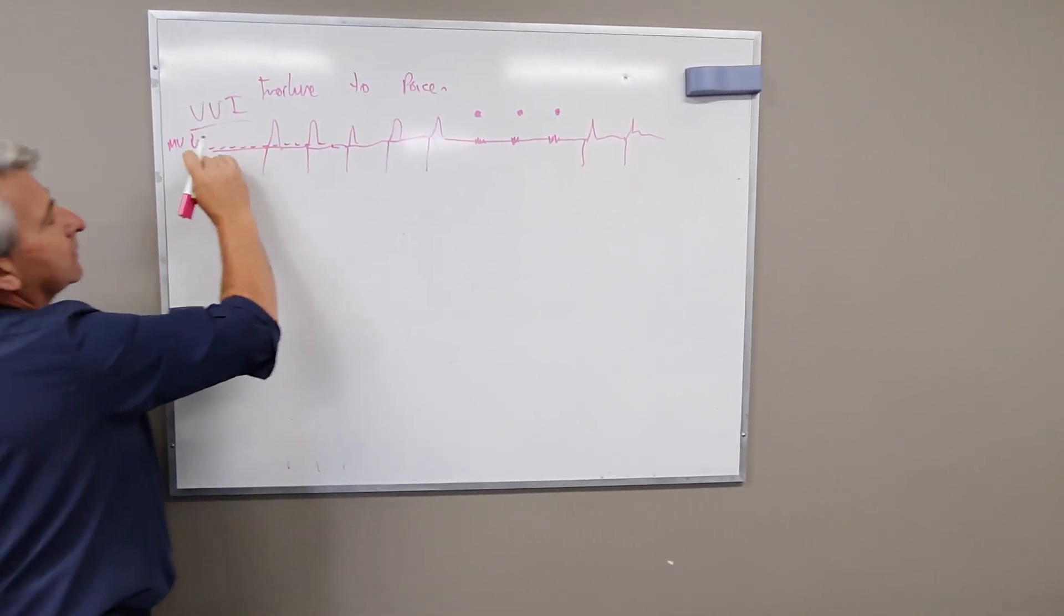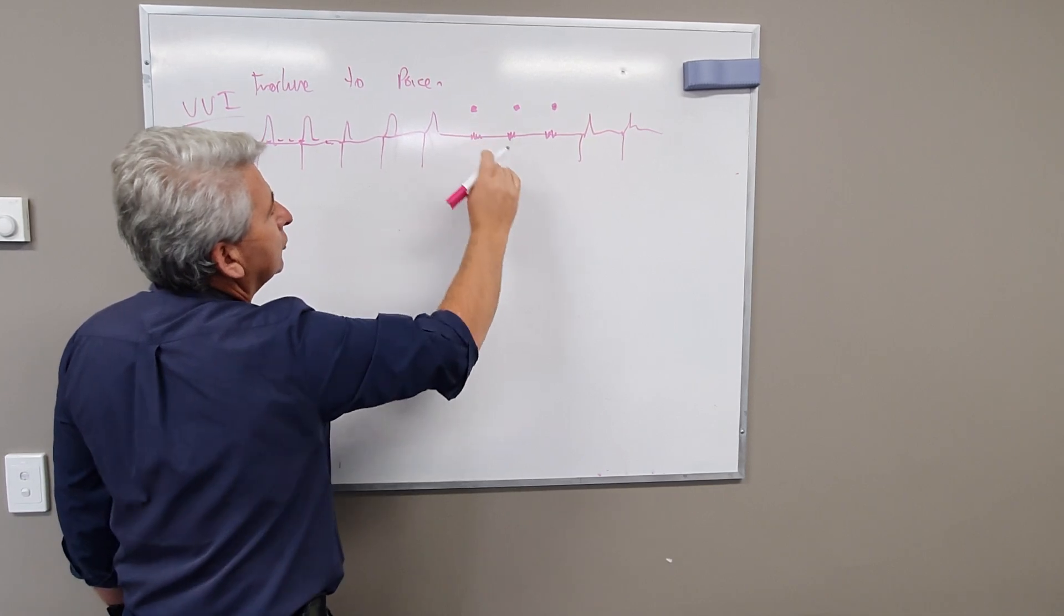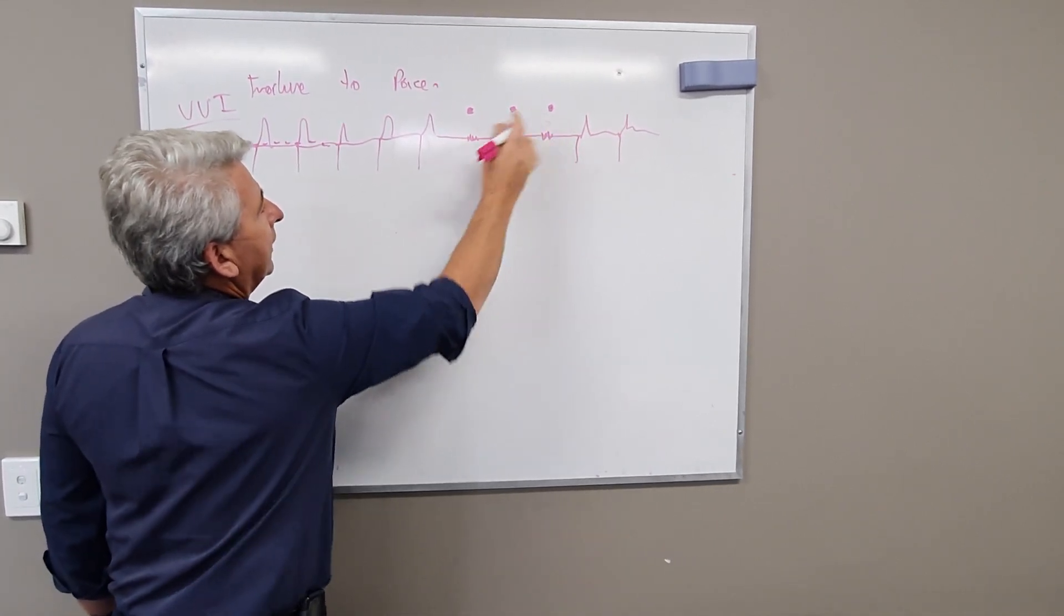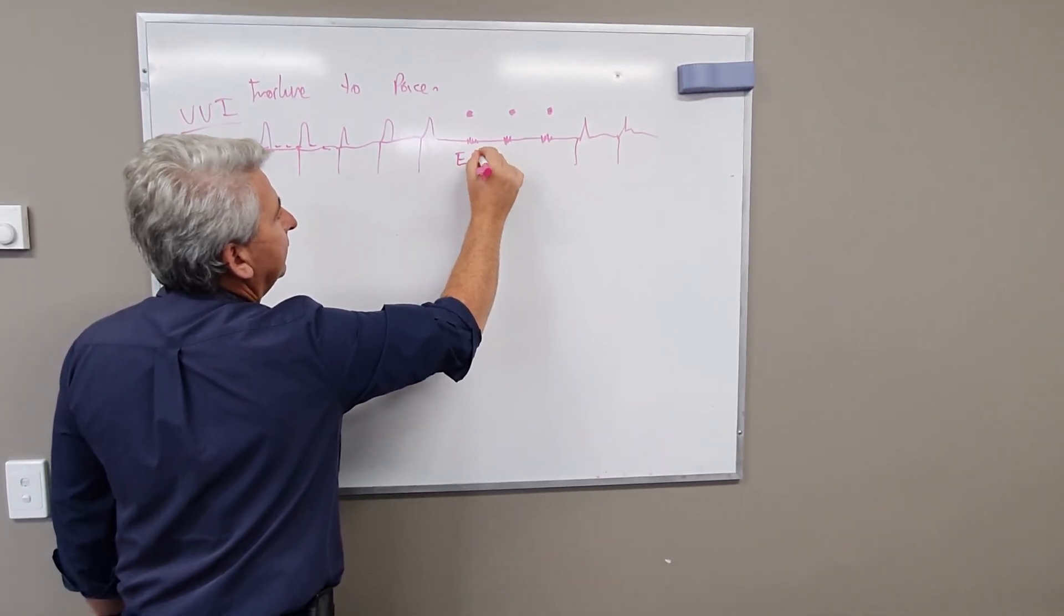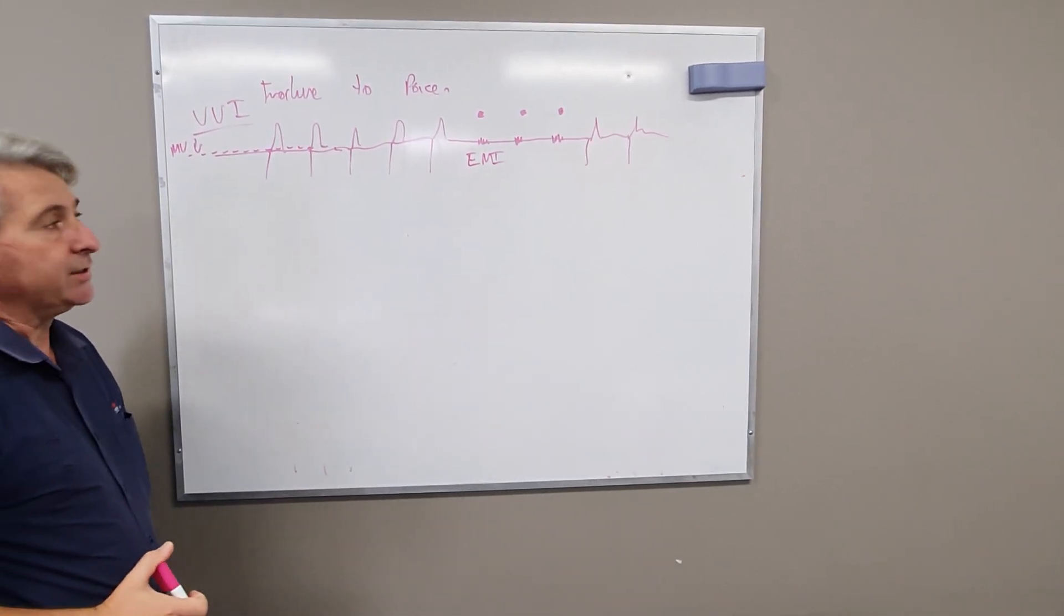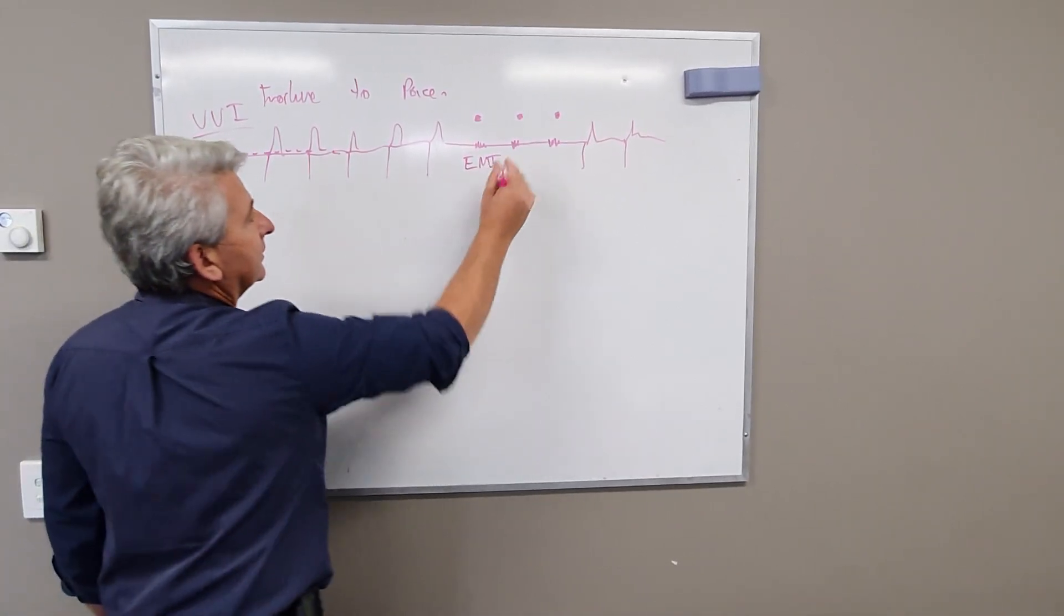So basically what the problem is here is the sensitivity line is way too low, so the millivolts are actually turned right down. So the fence is all the way down, seeing too much, and at this point it thinks this electromagnetic interference is some sort of intrinsic activity. So therefore it doesn't pace.